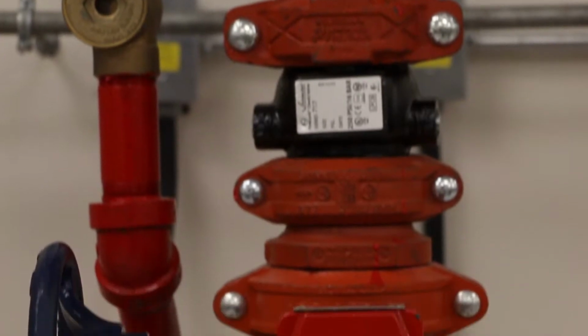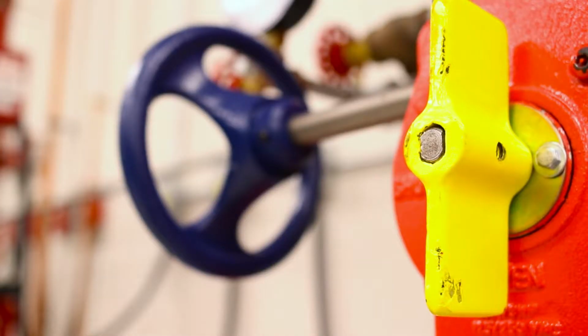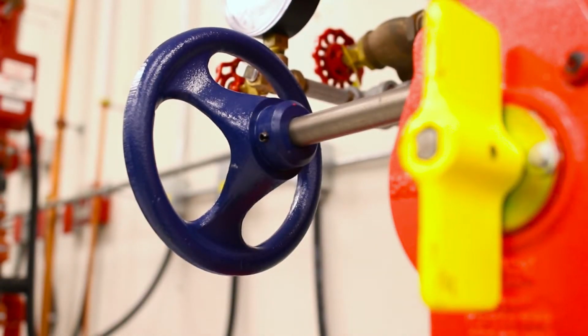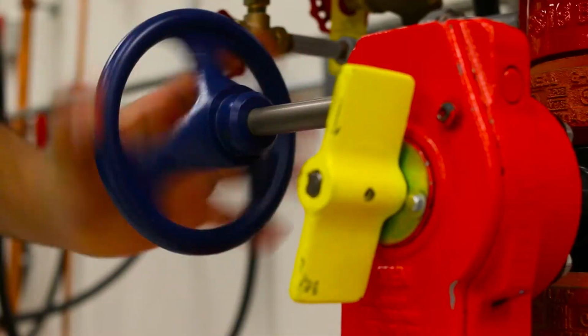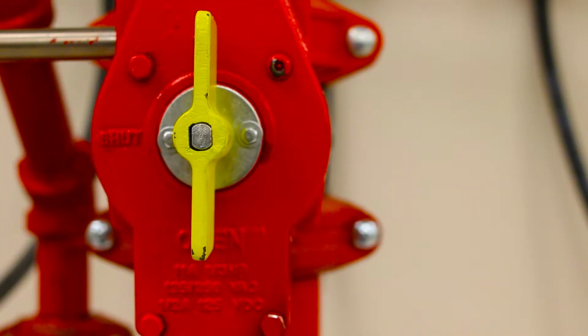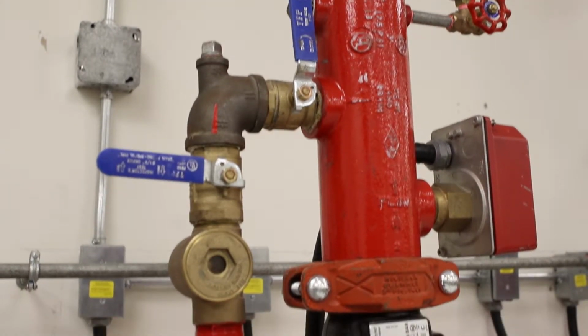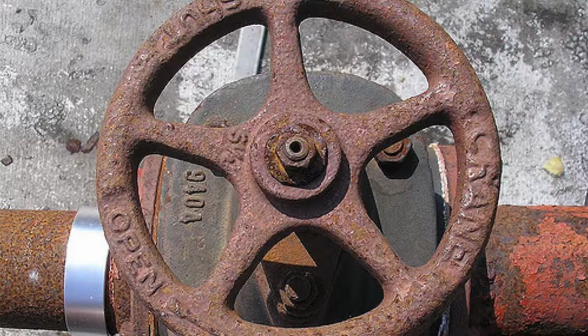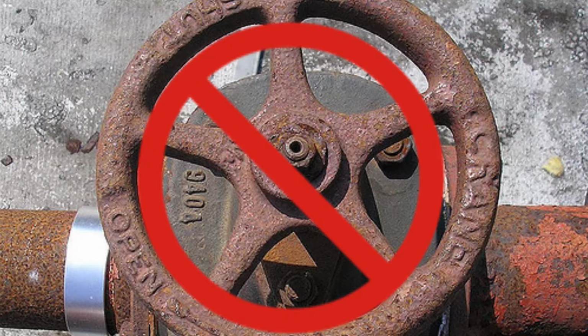It is always important to witness someone test the tamper valve properly. They should be turning the control valve wheel 1.5 turns to cause the fire alarm to activate a supervisory signal. If you see someone just click the lever on the tamper switch, that is not a valid test, so don't pay for it.